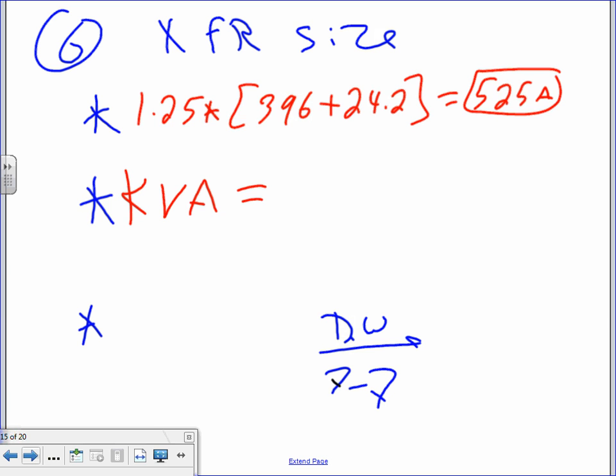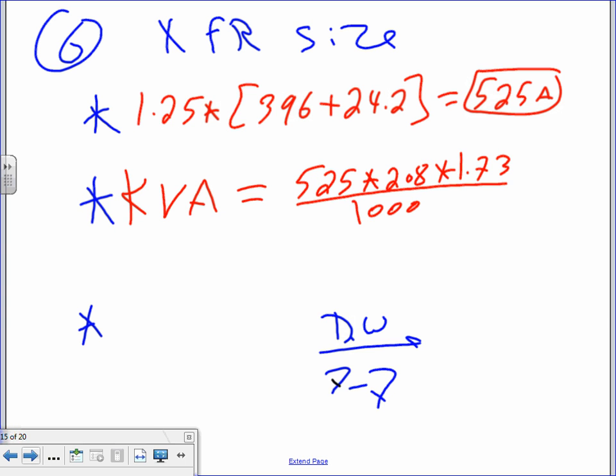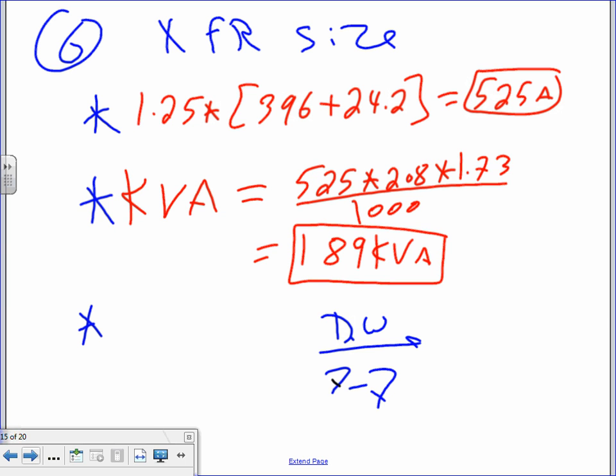Now you need to size, the transformers are sized in kVA. So you have to do the kVA for them. So you take this number, which is basically the 525, multiply it by, what's the voltage system? 208. What's the 1.73? It's 3-phase. Divide everything by 1,000 because kVA is in 1,000s. And when you go there, 189 kVA is the transformer that you need to buy.